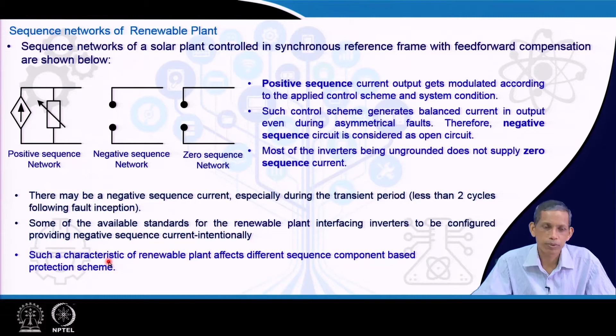Some of the available standards for renewable plant interface inverters ask for providing negative sequence current intentionally, so that the available protection and control schemes in the grid will still function properly. Such a characteristic of renewable plants affects different sequence component based protection schemes, and that raises the question of how the network protection schemes will perform.